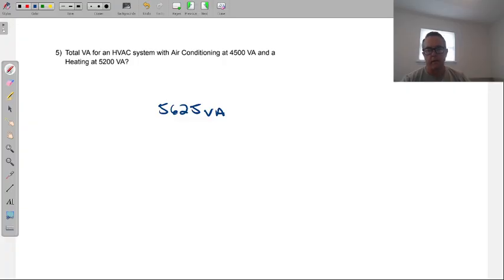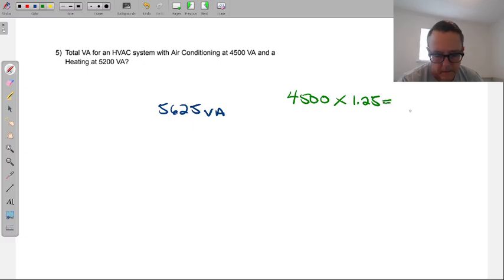So what would we do here? We have an HVAC system with an air conditioner at 4,500 VA and a heating unit inside at 5,200 VA. Those are the values. The heater's bigger, the HVAC smaller, but we increase the HVAC by 1.25 first. I'll put that math over here: 4500 times 1.25—and here's the correct answer, the correct number.